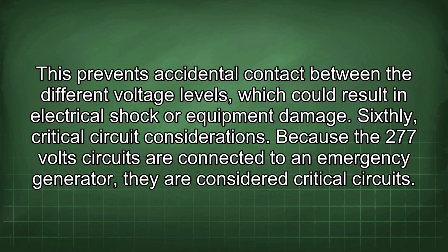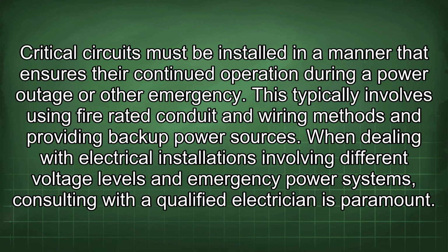Sixthly, critical circuit considerations. Because the 277 volt circuits are connected to an emergency generator, they are considered critical circuits. Critical circuits must be installed in a manner that ensures their continued operation during a power outage or other emergency. This typically involves using fire-rated conduit and wiring methods and providing backup power sources.